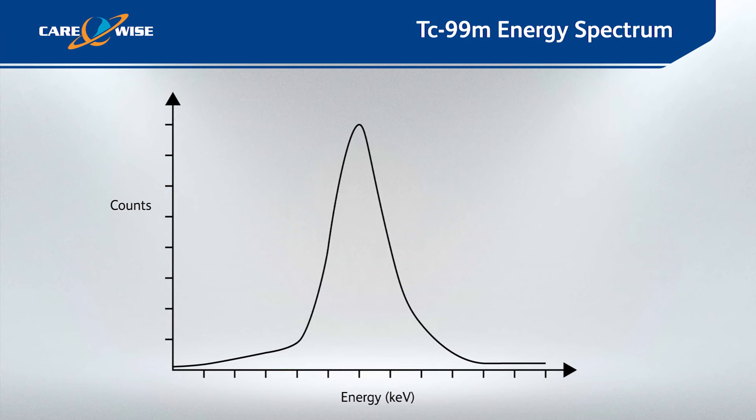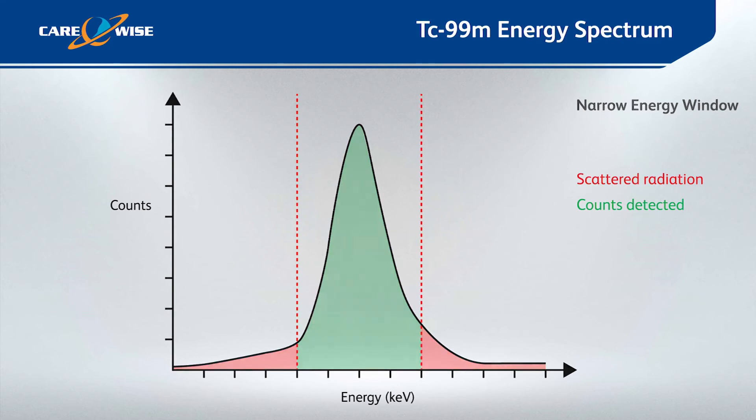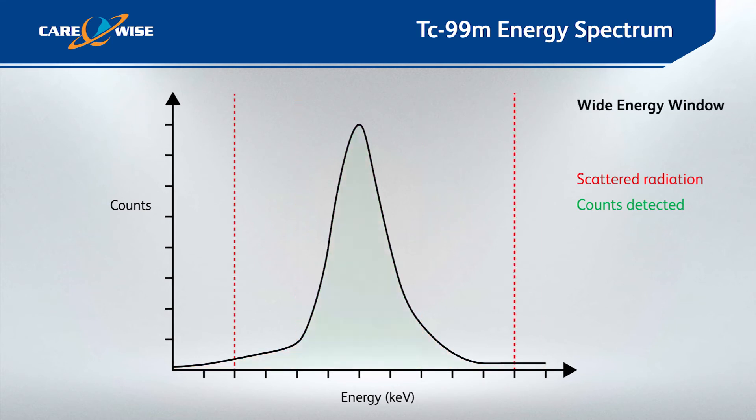The C-Trak system offers unrivaled directionality by differentiating between the gamma ray energies and uniquely eliminating scattered radiation from the counts detected. If for some reason the counts detected are poor, then you can select a wide energy window, which increases sensitivity but at the compromise of directionality. This is sometimes useful if the patient has had previous surgery or if they were injected over 24 hours before.